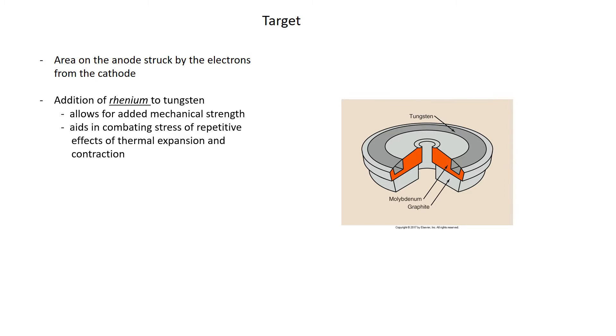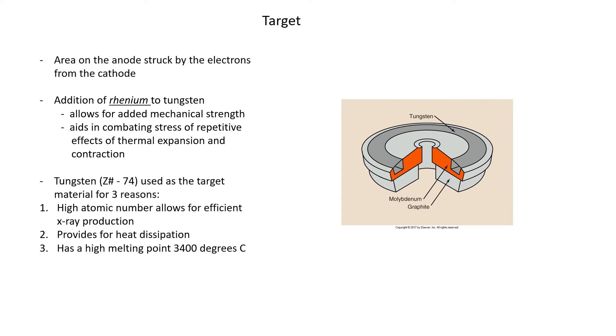Remember, when metal is heated it expands; when it's cooled, it contracts. Tungsten is used as the target material for three primary reasons: it has a high atomic number which allows for efficient x-ray production; it provides good heat dissipation; and it has a very high melting point of 3,400 degrees Celsius.